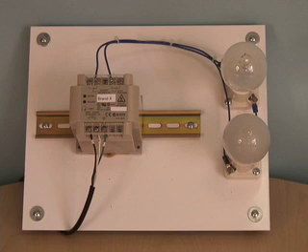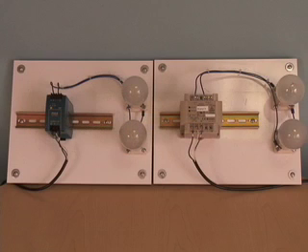Because this 50 watt power supply was unsuccessful in starting the load, a larger unit would have to be installed. This is one of many reasons why users oversize their power supplies.